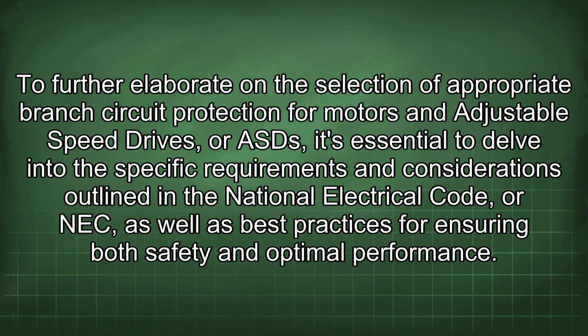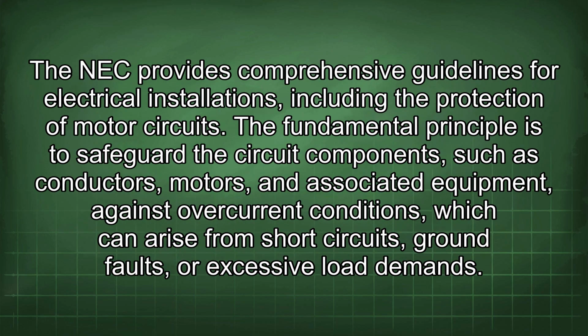To further elaborate on the selection of appropriate branch circuit protection for motors and adjustable speed drives, it's essential to delve into the specific requirements and considerations outlined in the National Electrical Code, or NEC, as well as best practices for ensuring both safety and optimal performance. The NEC provides comprehensive guidelines for electrical installations, including the protection of motor circuits. The fundamental principle is to safeguard the circuit components, such as conductors, motors, and associated equipment, against overcurrent conditions which can arise from short circuits, ground faults, or excessive load demands.